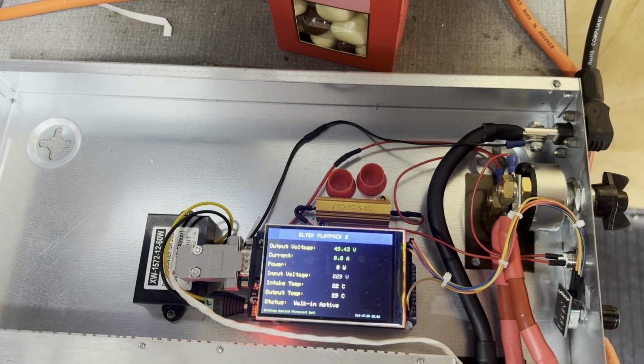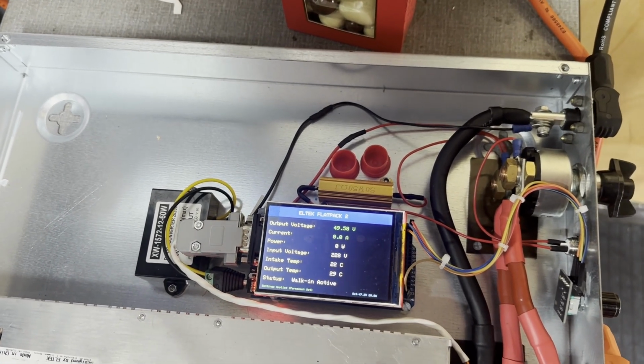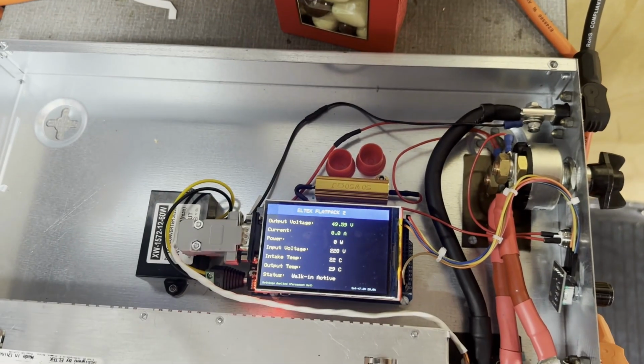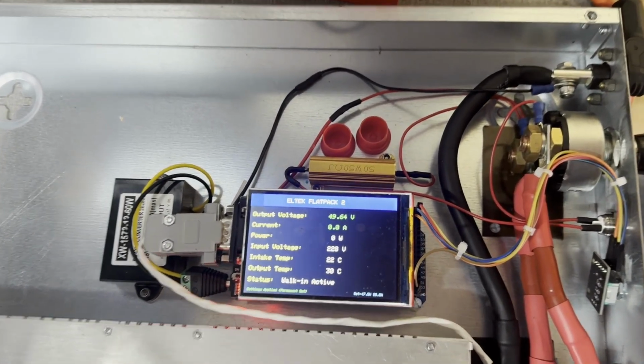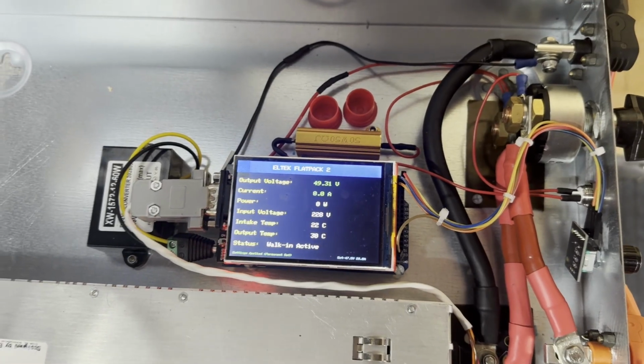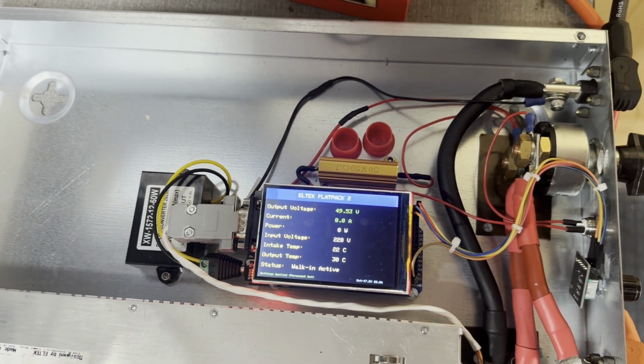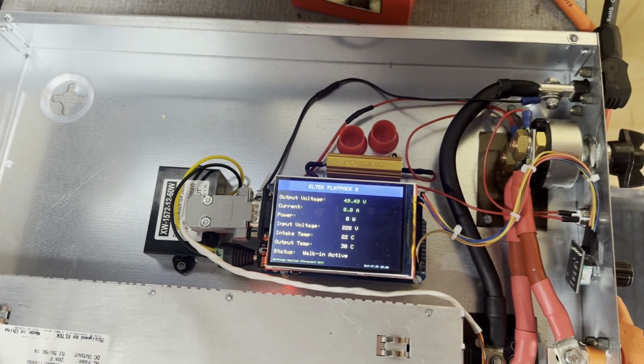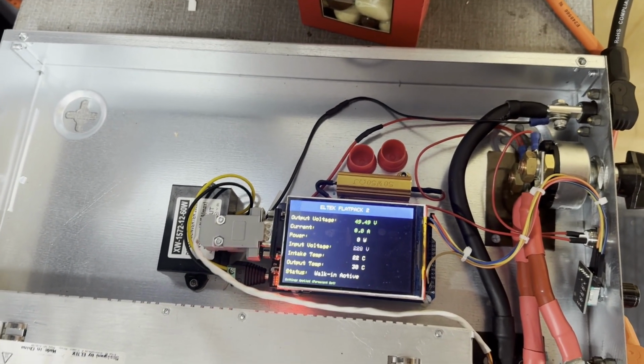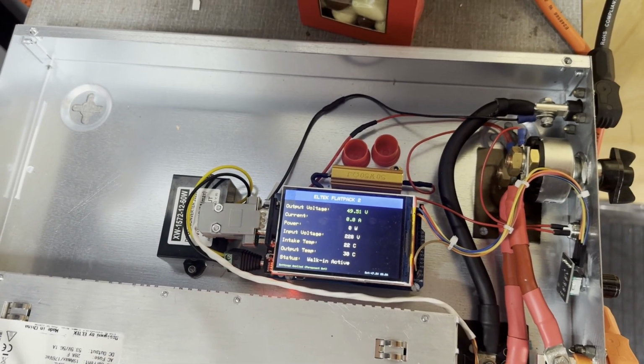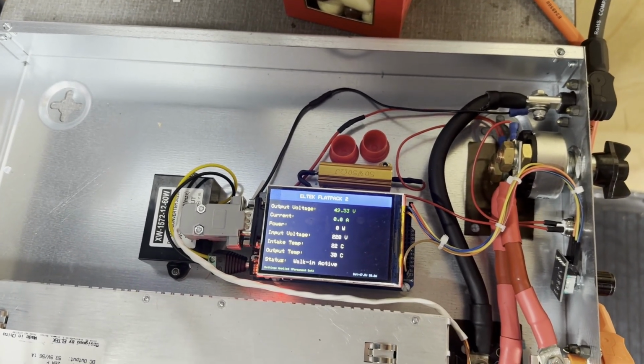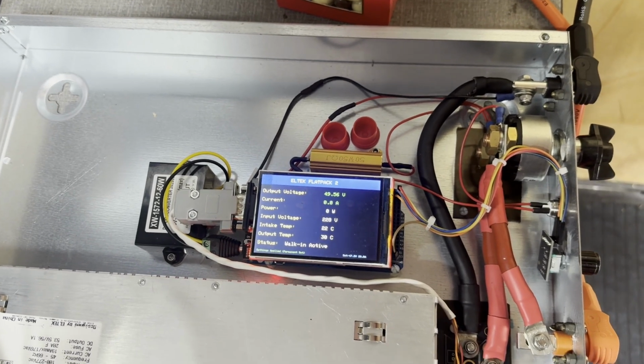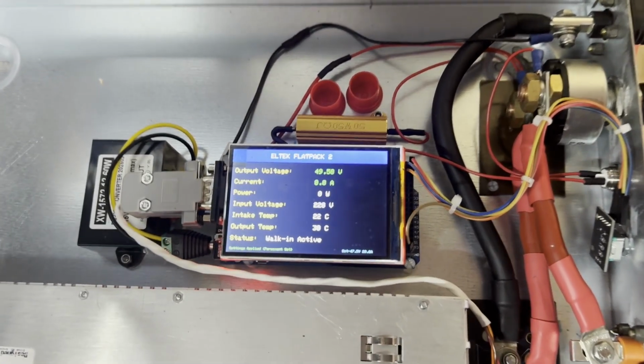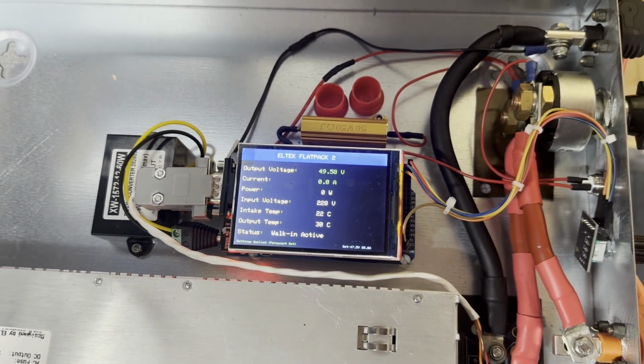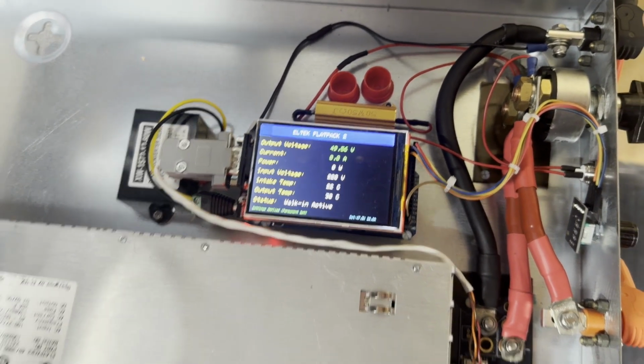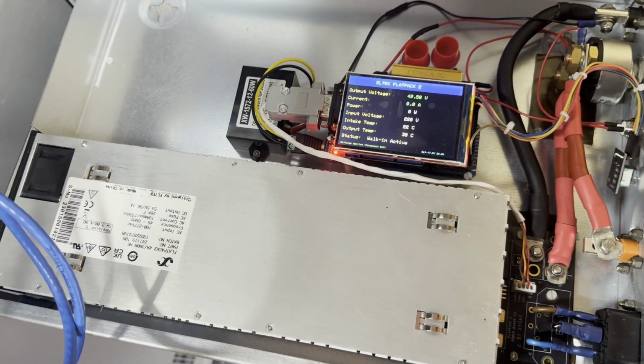I think it's got a continuous rating of about 2.6 kVA. I don't know what the power factor is. I run it at about 2,500 watts maximum, so I've coded it so I can't draw more than 2,500 watts. I've done that through the maximum voltage, which is about 51.5 volts, about 80% charge. Again, I've deliberately not gone for 100% charge, and I've limited the current to 50 amps, which takes you up to about 2,500. So I've hard-coded parameters in there around the maximum that the generator can do. The power supply is capable of more, but I don't really want to run it flat out.